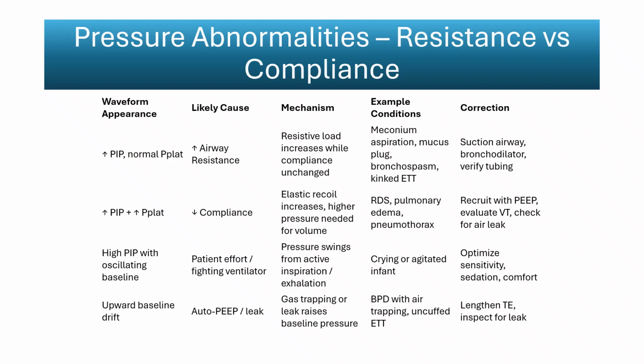High peak inspiratory pressure with an oscillating baseline reflects active patient effort. The infant is either fighting the ventilator or breathing asynchronously, generating pressure swings on top of the ventilator-delivered pressure. Crying, discomfort, or agitation causes rapid fluctuations in the pressure tracing. Optimizing trigger sensitivity, improving comfort, and addressing pain or agitation helps stabilize this pattern.